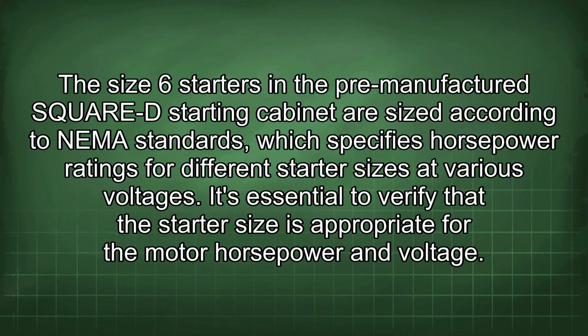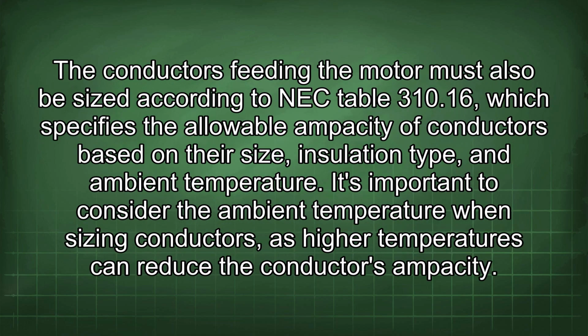The size 6 starters in the pre-manufactured Square D starting cabinet are sized according to NEMA standards, which specify horsepower ratings for different starter sizes at various voltages. It's essential to verify that the starter size is appropriate for the motor horsepower and voltage. The conductors feeding the motor must also be sized according to NEC Table 310.16, which specifies the allowable ampacity of conductors based on the size, insulation type, and ambient temperature. It's important to consider the ambient temperature when sizing conductors, as higher temperatures can reduce the conductor's ampacity.